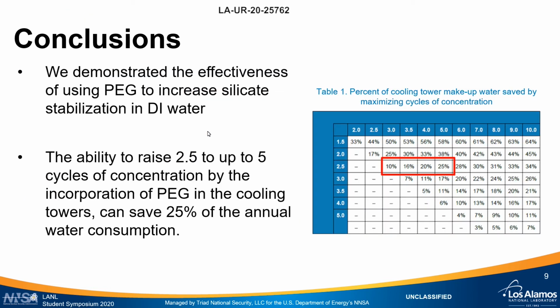In conclusion, we demonstrated the effectiveness of using PEGs to increase silicate stabilization in deionized water. Recall that the percent silicate stabilization for 20K molecular weight PEG at 200 ppm is about 70%. By applying PEGs to the cooling systems, if it can help raise the cycles of concentration from 2.5 to 5, this could save about 25% of annual water consumption, which is very good and very helpful.